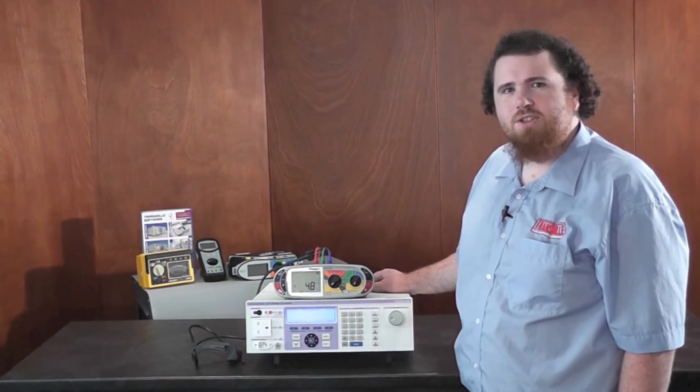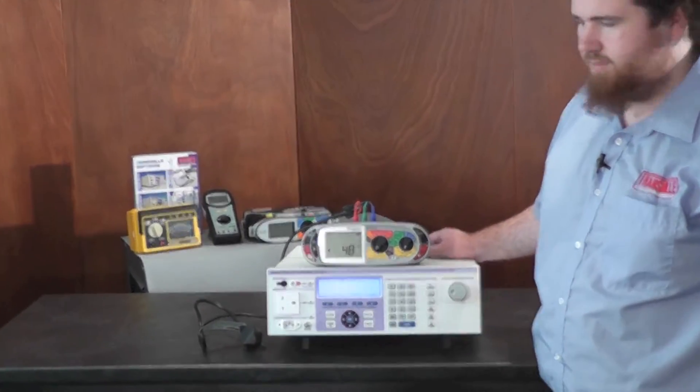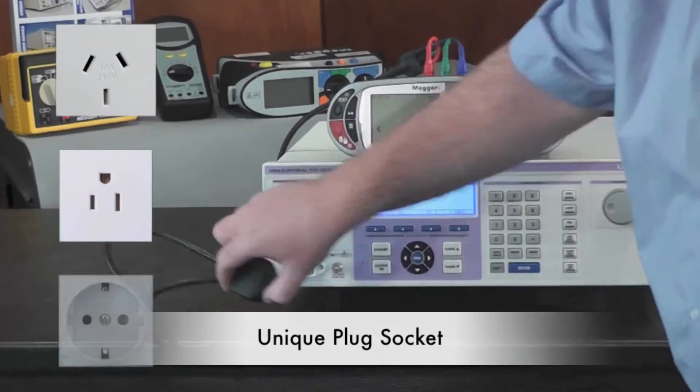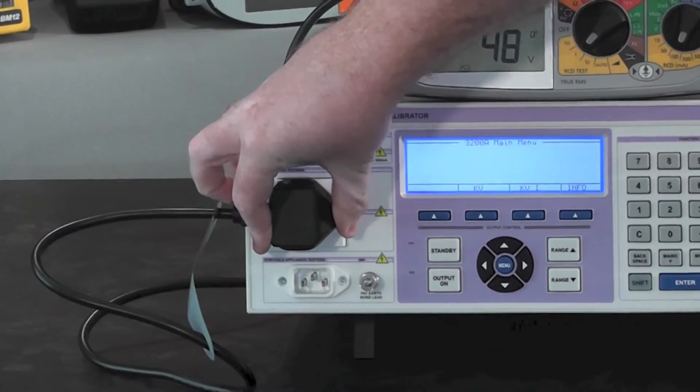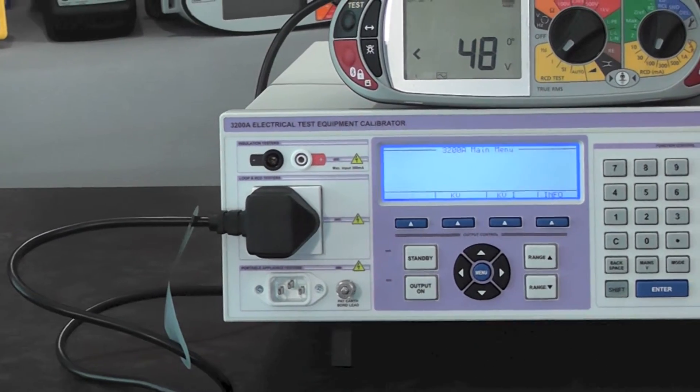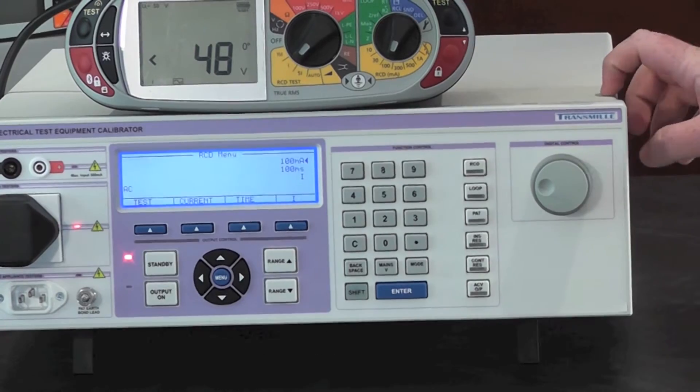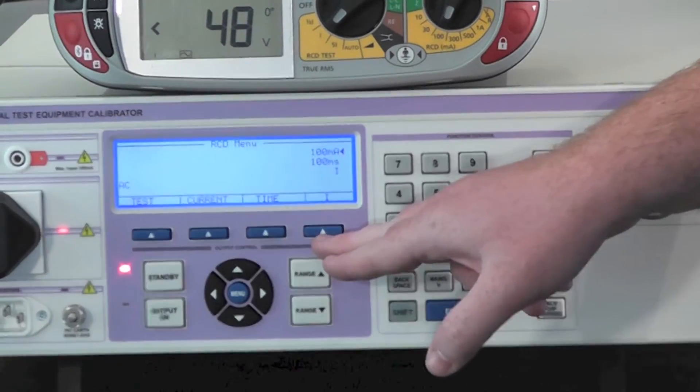Calibrating RCD testers with the 3200A is quick and safe. Using Transmille's unique plug socket on the front of the 3200A testers simply plug in. Using the dedicated RCD key you can then select the current, the time and the current mode required.